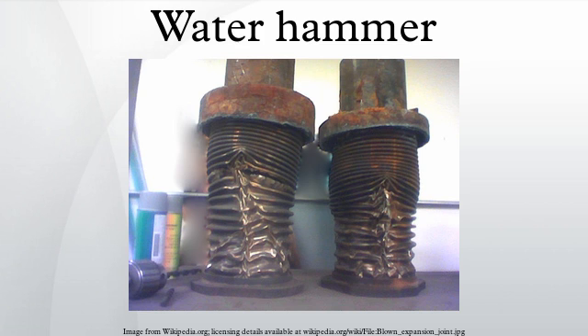Instant valve closure. Compressible fluid. The pressure profile of the water hammer pulse can be calculated from the Joukowski equation. So for a valve closing instantaneously, the maximum magnitude of the water hammer pulse is, where ΔP is the magnitude of the pressure wave, ρ is the density of the fluid, a0 is the speed of sound in the fluid, and Δv is the change in the fluid's velocity.